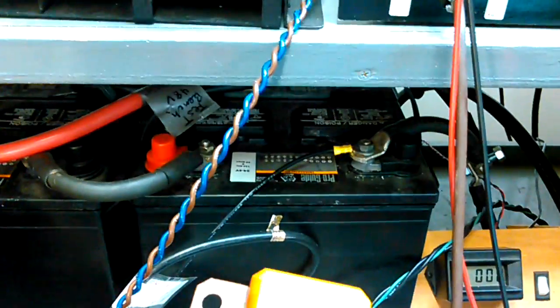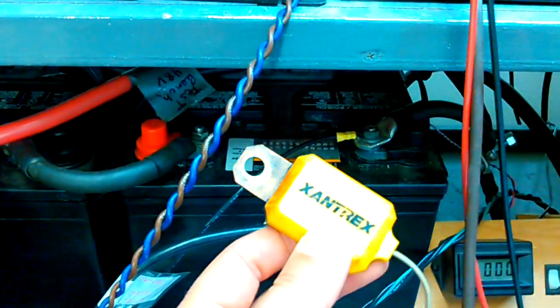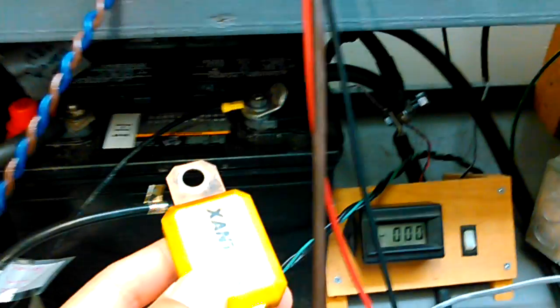The idea is that if I bolt this right to the terminal on the battery, the temperature in the battery is going to come out to the terminals, and it's going to be a better reading of the actual battery temperature. But here's something you have to consider. If you want to use it on the terminal, you've got to be careful, because if you have your main positive feed wire coming in, and that wire's carrying 100, 200 amps when your inverter's running a good load, this terminal's going to get hot. And that's normal. When you have that much current running through a wire, it gets warm. So it really isn't an actual reflection of the overall temperature of the battery itself, and it can give you a false over-temp reading.